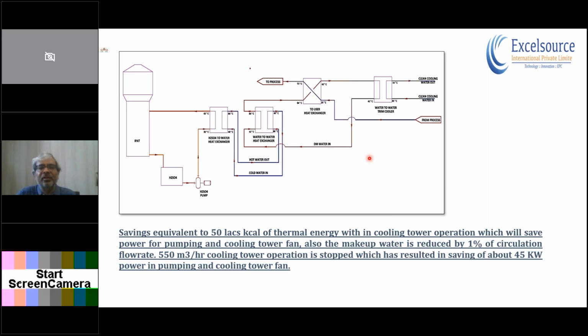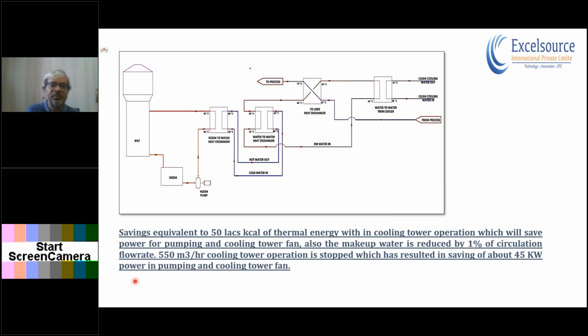And this hot water we have taken into use. This was actually implemented in South Africa, in Central Africa and DR Congo, where the heat is utilized in the leaching process of the plant, wherein at that particular point of time they were using low pressure steam. 2 bar or 3 bar steam was used for heating the leaching solutions to extract more metal from the product from the mines. So this heat was utilized to eliminate the operation of the boiler by stopping the boiler. Diesel was saved. There is no coal availability in the DR Congo area, it is diesel, so almost more than 35 crores of saving was established by implementation of this particular pinch technique.